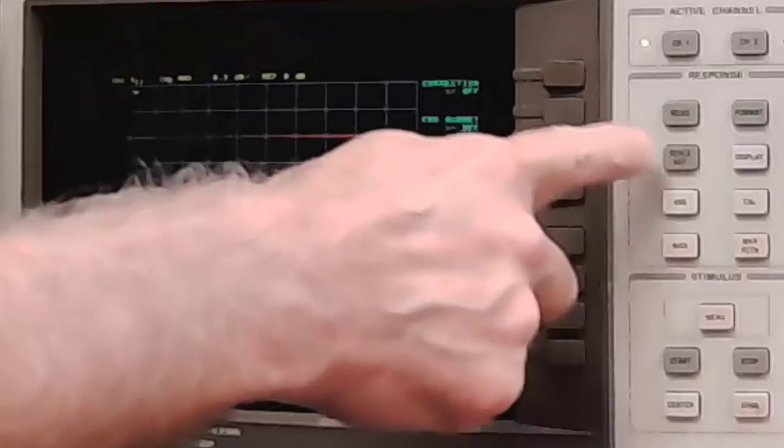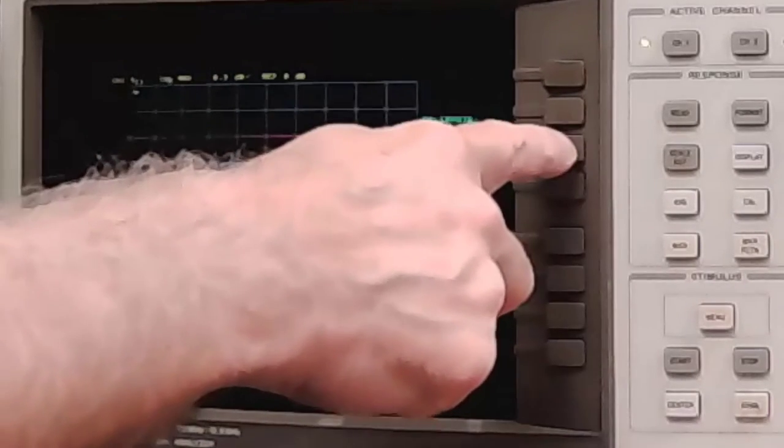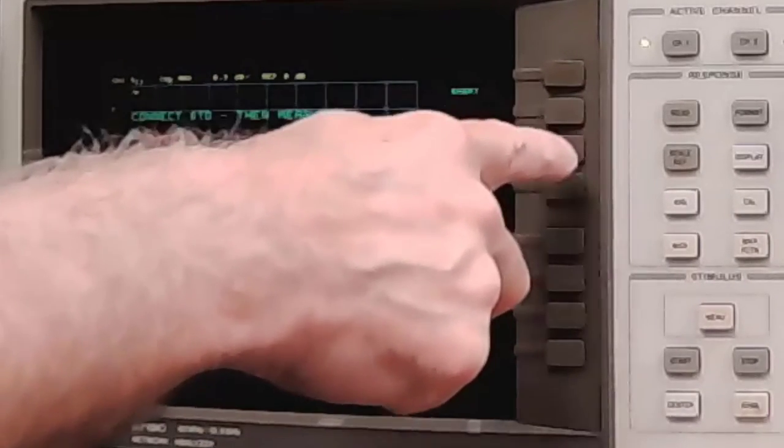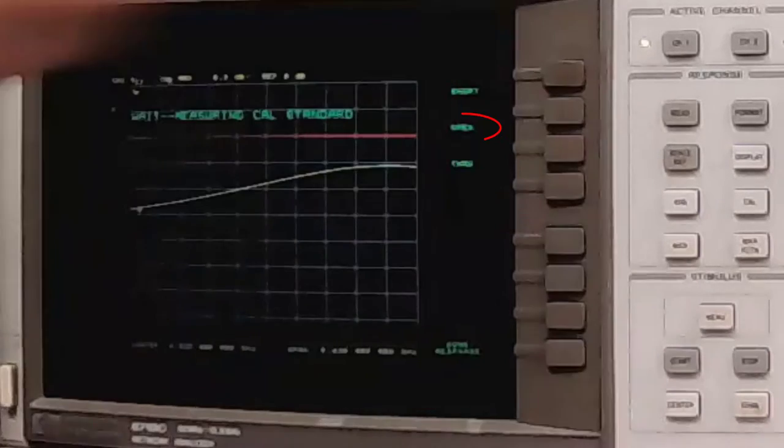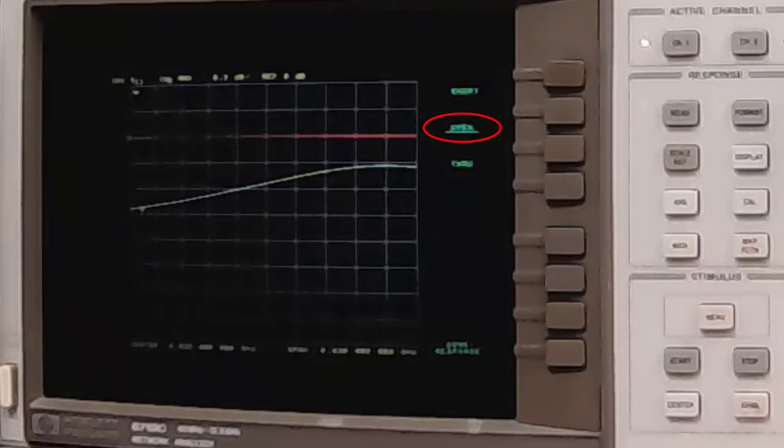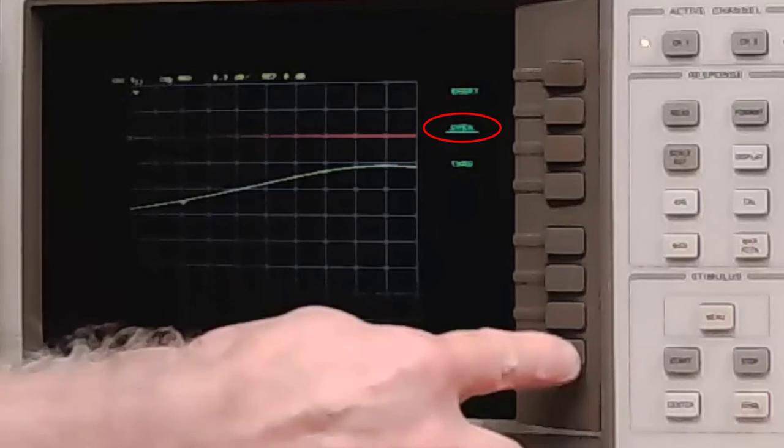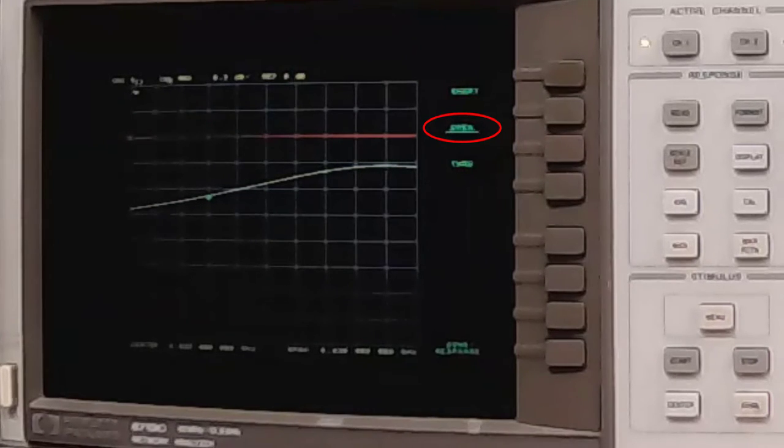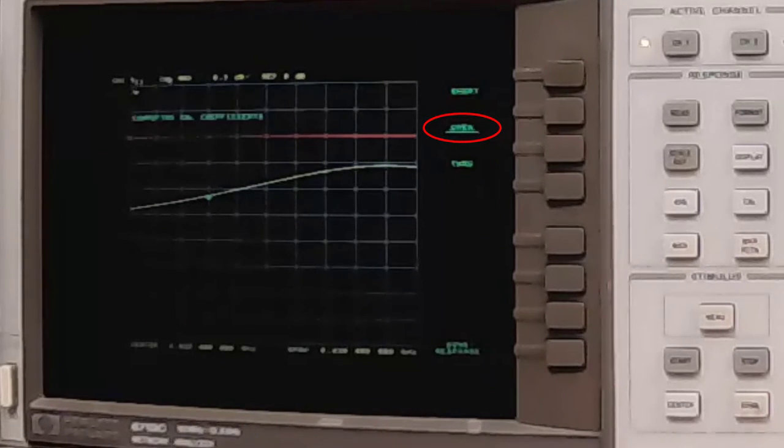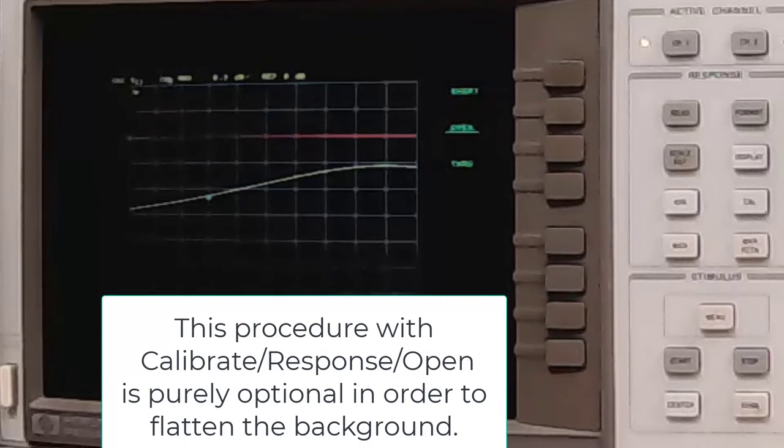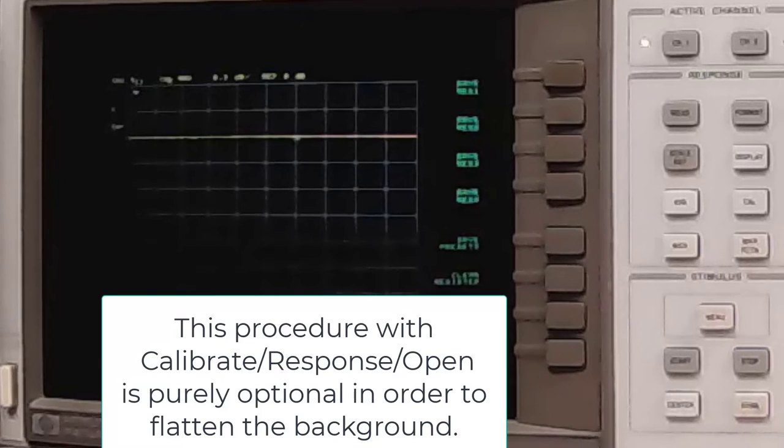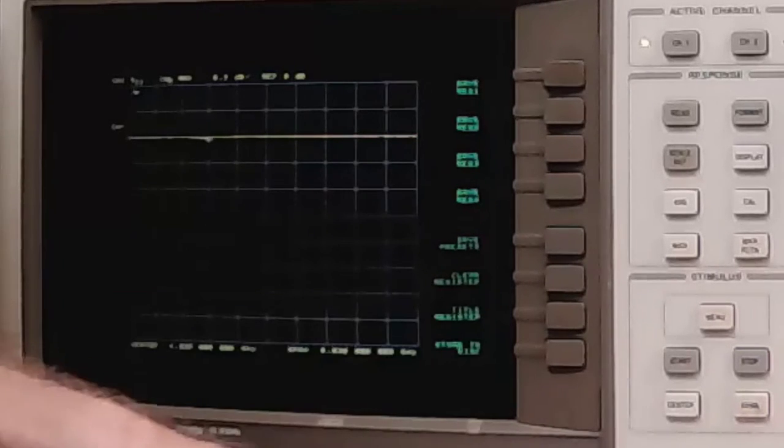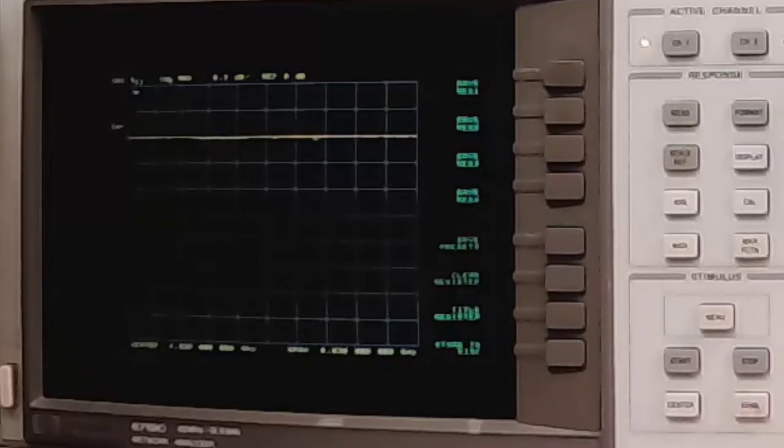Push Cal, Calibrate Menu, Response, and Open. And it will measure the open circuit calibration coefficients. I'll push Done, and you'll notice we have a horizontal line. I have gotten rid of the background. I have not calibrated the network analyzer. You will not get a meaningful VSWR, but you will get a flat response. I'm going to retune the resonance now.